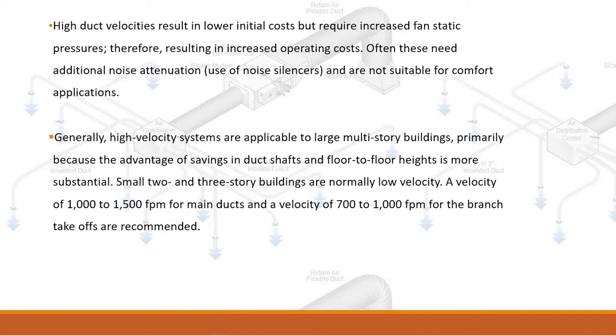High velocity systems often need additional noise attenuation using noise silencers and are not suitable for comfort applications. They are generally applicable to large multi-story buildings, primarily because savings in duct shafts and floor-to-floor heights are more substantial. Small two and three-story buildings are normally low velocity. A velocity of 1000 to 1500 FPM for main ducts and 700 to 1000 FPM for branch take-offs are recommended.